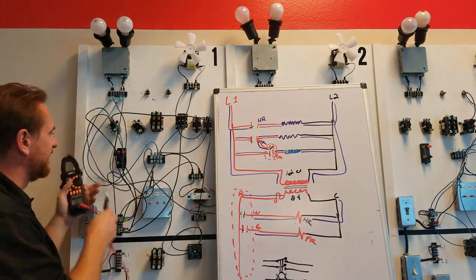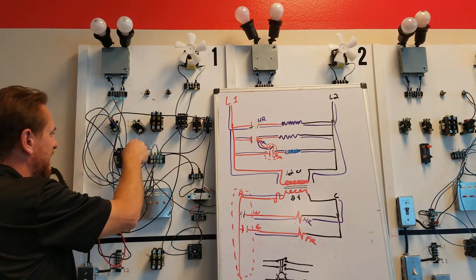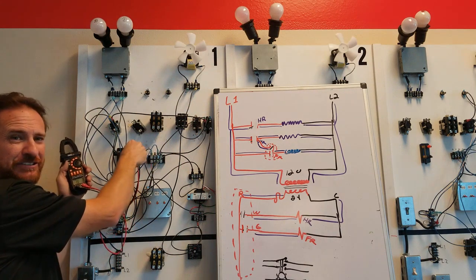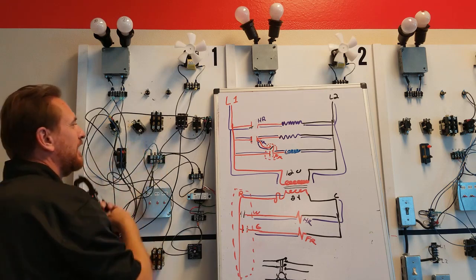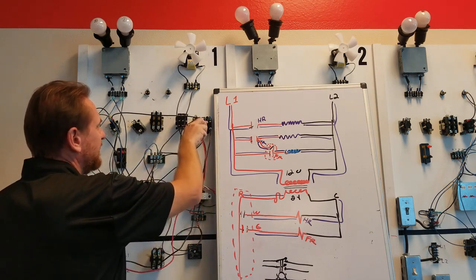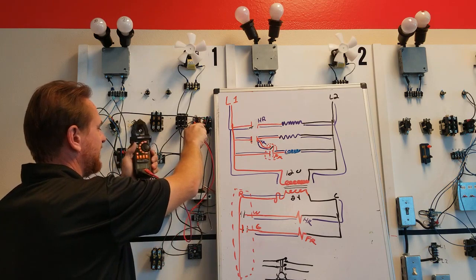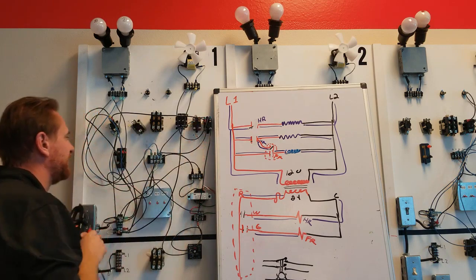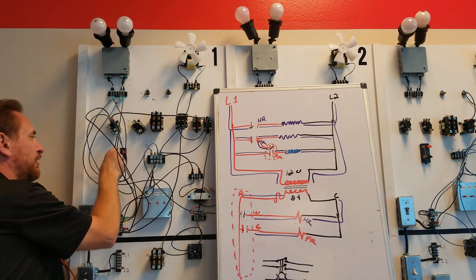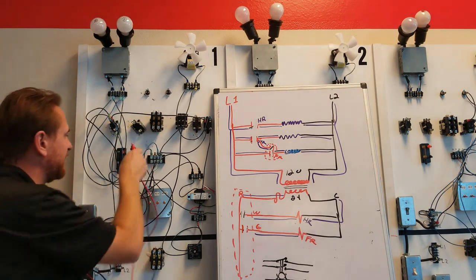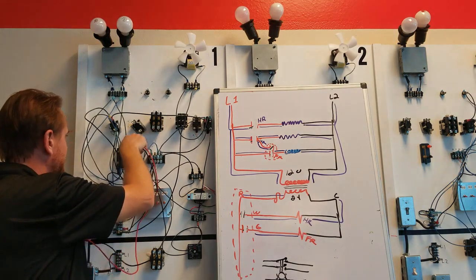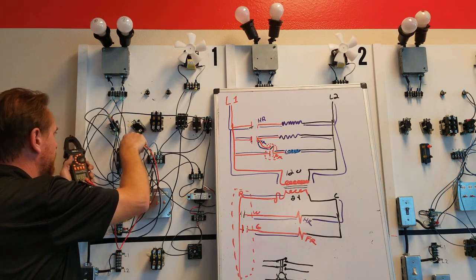We can see this knife blade switch. The switch is open, and I have OL, infinite resistance. Electrons cannot flow. I check between the next bottom set down here, and this, I get 0 resistance. There is no resistance. That would be this switch being closed. There is nothing to slow it down. If I check here and here, with the switch closed, I get resistance.